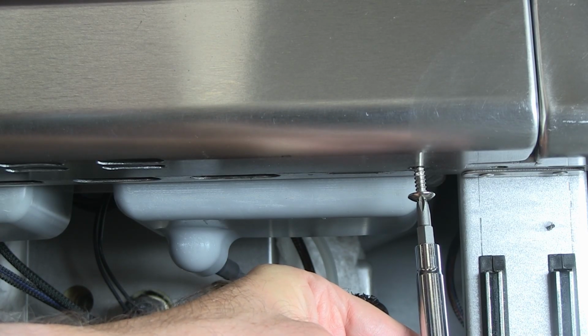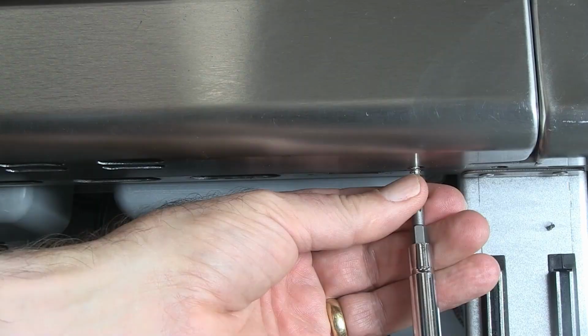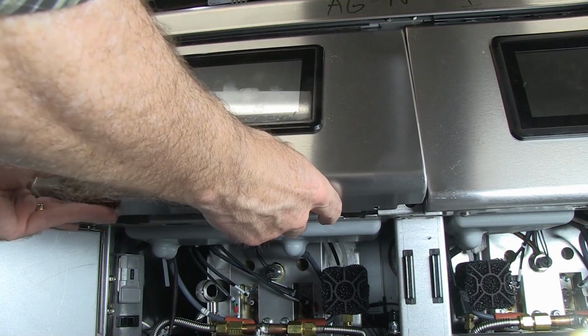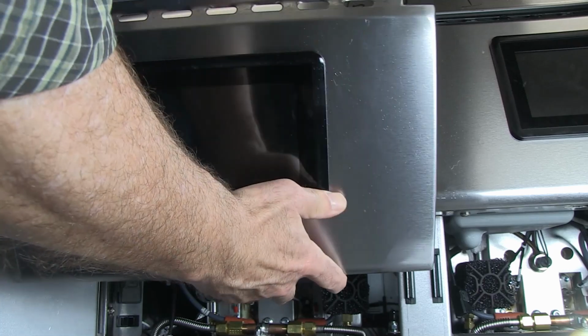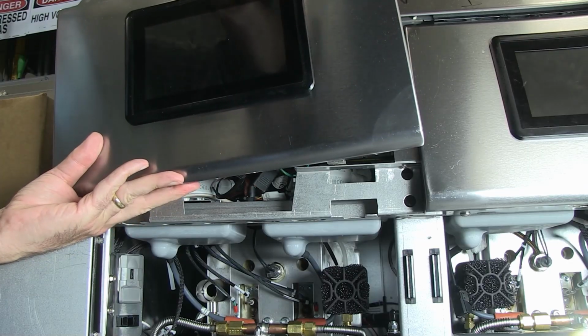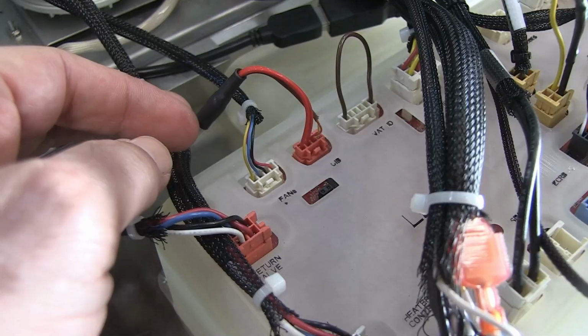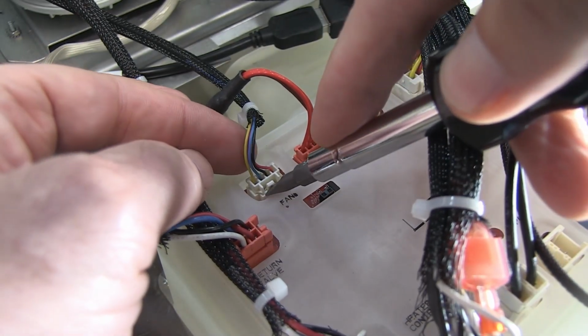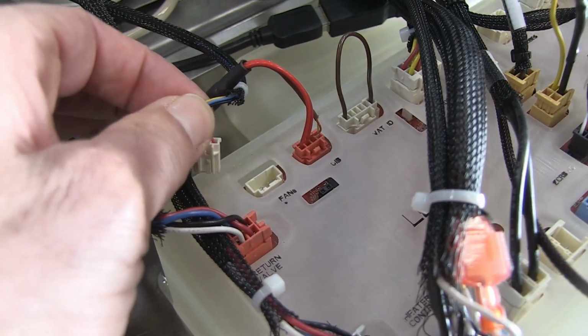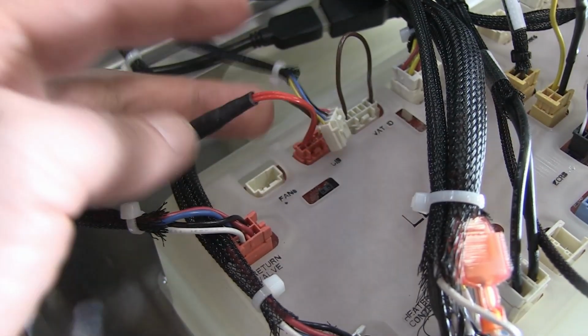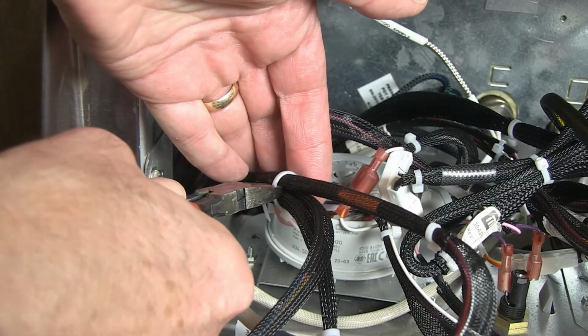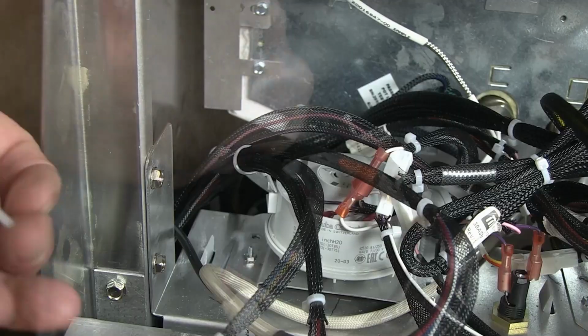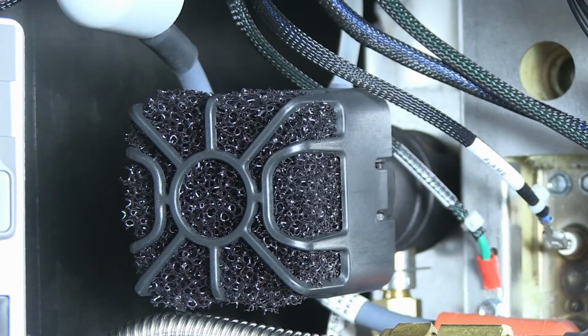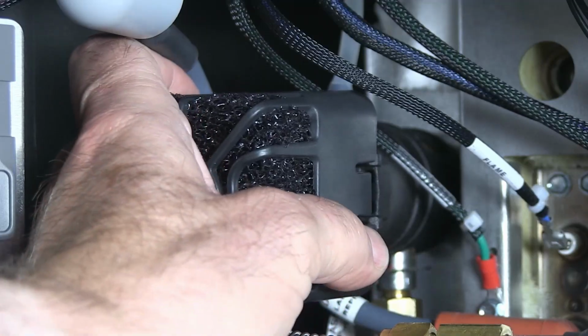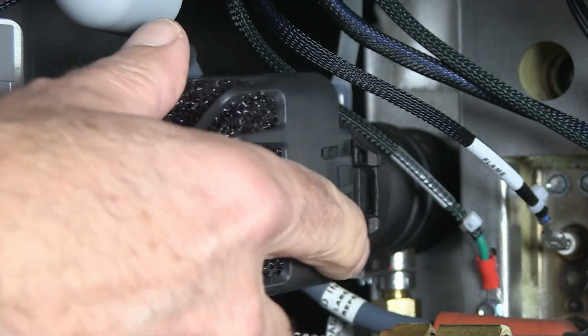Replacing the fan requires removing the bezel to access its wiring. Remove the screws securing the bezel to the frame. Hook the bezel's tabs into the higher retention points below the control box. Remove the plug from the back of the controller, the HCB. Press the tab with a fingernail or small screwdriver blade. Remove the wire ties attaching the fan wire to the adjacent wires. Push the wire through the opening and below the control box. Press the tabs on both sides of the filter of the failed fan and pull to remove it.